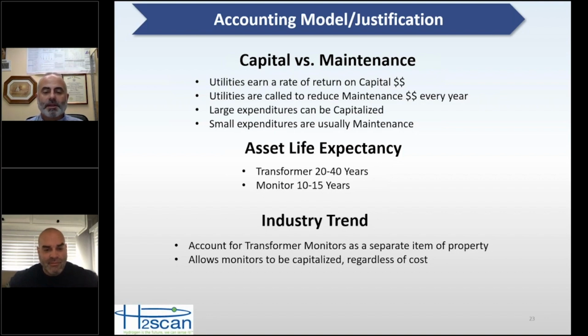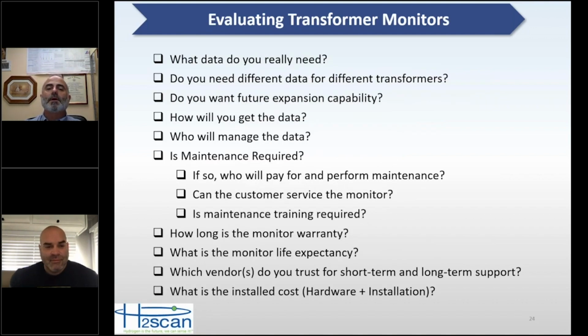So the industry trend is more and more utilities are starting to put a transformer monitor as a separate item of property on the books. So when that power transformer is purchased with a monitor, the monitor goes on the books as a separate item of property. So if it needs to be replaced in 10 or 15 years, that can be a capital replacement rather than a maintenance replacement. So that's a very nice thing, being able to justify installing hydrogen monitors.